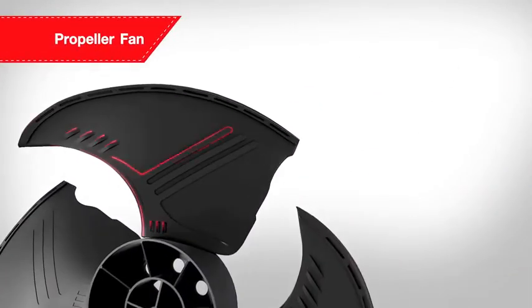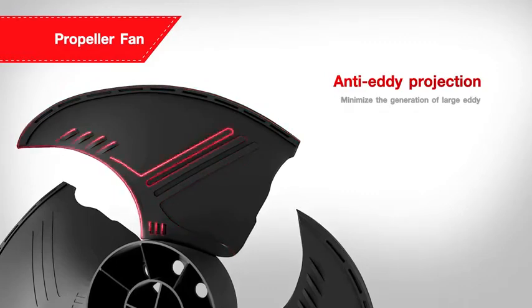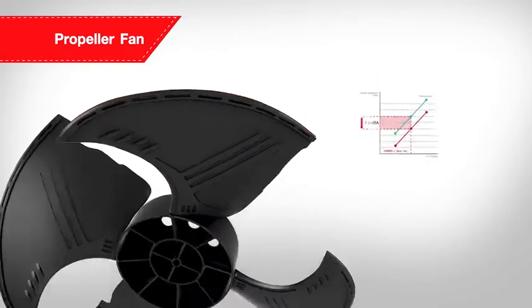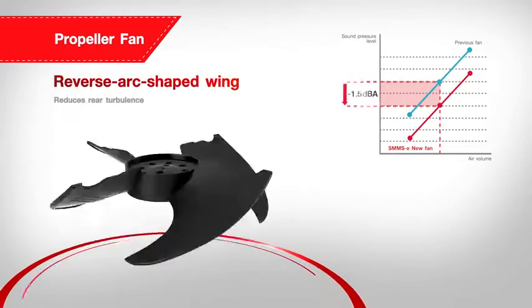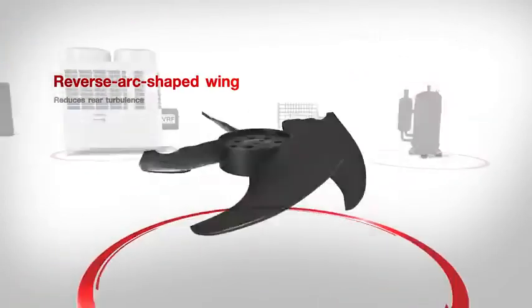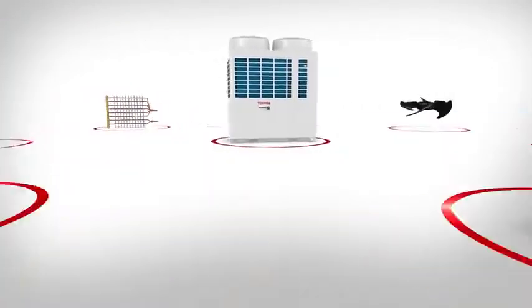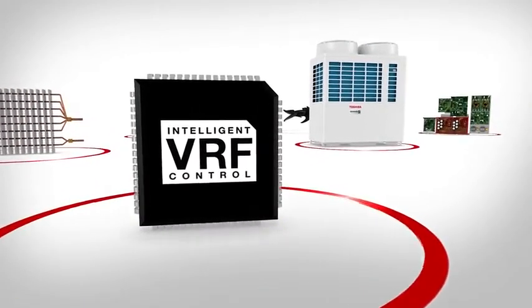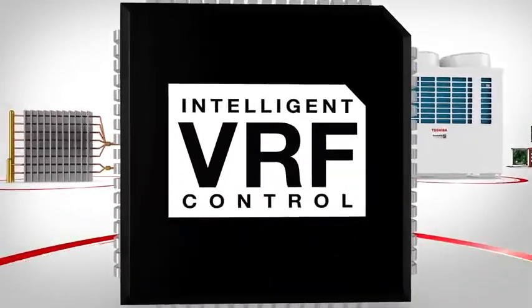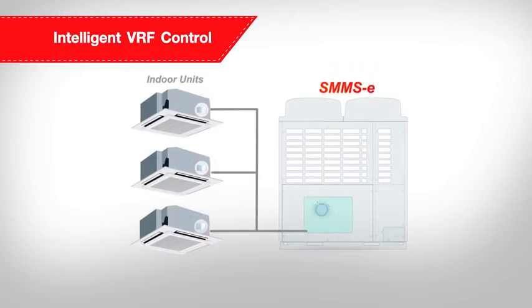The SMMS-e is designed with new propeller fan to minimize the generation of large eddy, with reverse arc-shaped wing to reduce rear turbulence. The intelligent VRF control, Toshiba's technology in SMMS-e, can help control the flow of refrigerant to each indoor unit via independent PMV control.